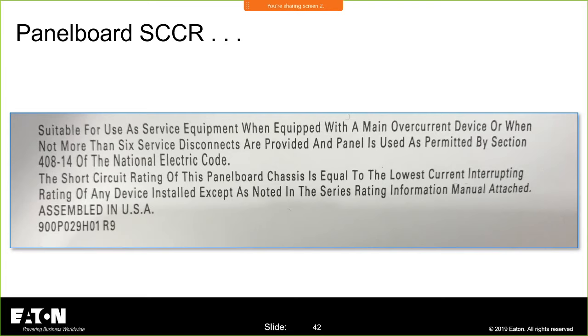And then you go to the supply house because you're going to add a new breaker and you say, hey, I need a 20 amp breaker. What do you think they're going to throw on the table? A 22K breaker or a 10K breaker? They are probably going to give you a 10K breaker and not a 22K breaker. And the moment you put that breaker in this panel board, you just reduced the short circuit current rating from 22K to 10K.